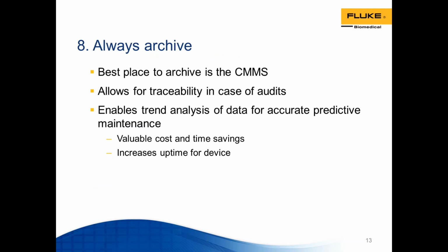Number 8, always archive. The best place, of course, to archive is the CMMS, or Computerized Maintenance Management System. That's a database. Best place to keep our measurements and the records is really in that database. This allows for traceability in case of audits. It enables the trend analysis of data for accurate predictive maintenance when the database is prepared with a long-term statistical analysis capability. Databases are much more powerful than your local computer and can run that long-term trend, and by that you will actually be able to get to predictive maintenance and be able to schedule when that ESU is going to be taken out of clinical use long enough to do some scheduled replacement or repair. So that's where we really want to be, is at the predictive maintenance level.